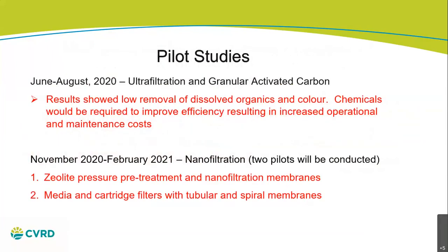So one pilot study we did this summer used one technology called ultrafiltration and granular activated carbon together. We ran just one and just the other and then together to see whether we'd be able to reduce our dissolved organics and meet the requirements. Unfortunately, although it does meet the requirement for filtration with respect to bacteria and viruses, it doesn't meet it with respect to the removal of the organics. And when I say unfortunately, it's because ultrafiltration and activated carbon would be cheaper than the higher requirements that we'd have to meet. So we looked at that, but that's not going to do it.